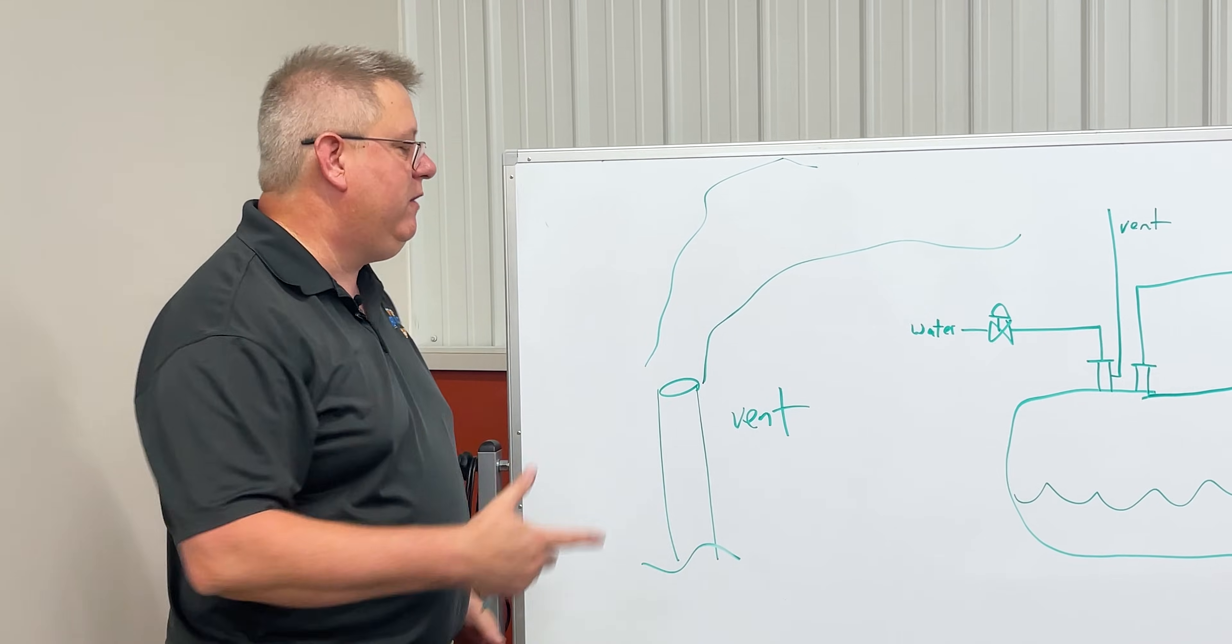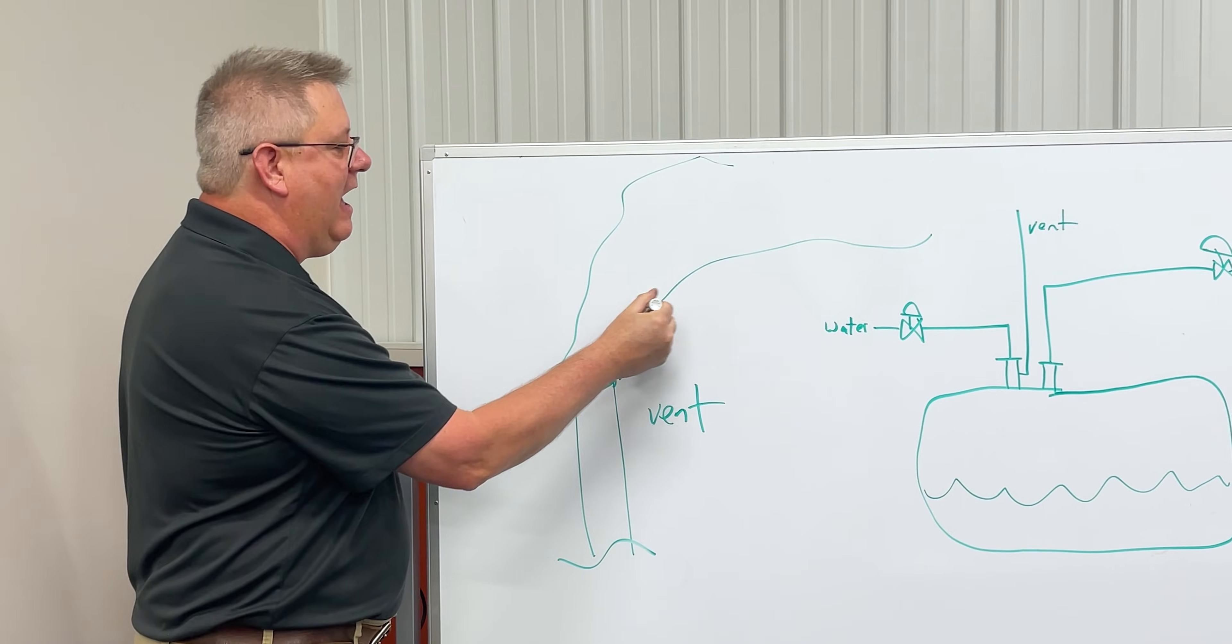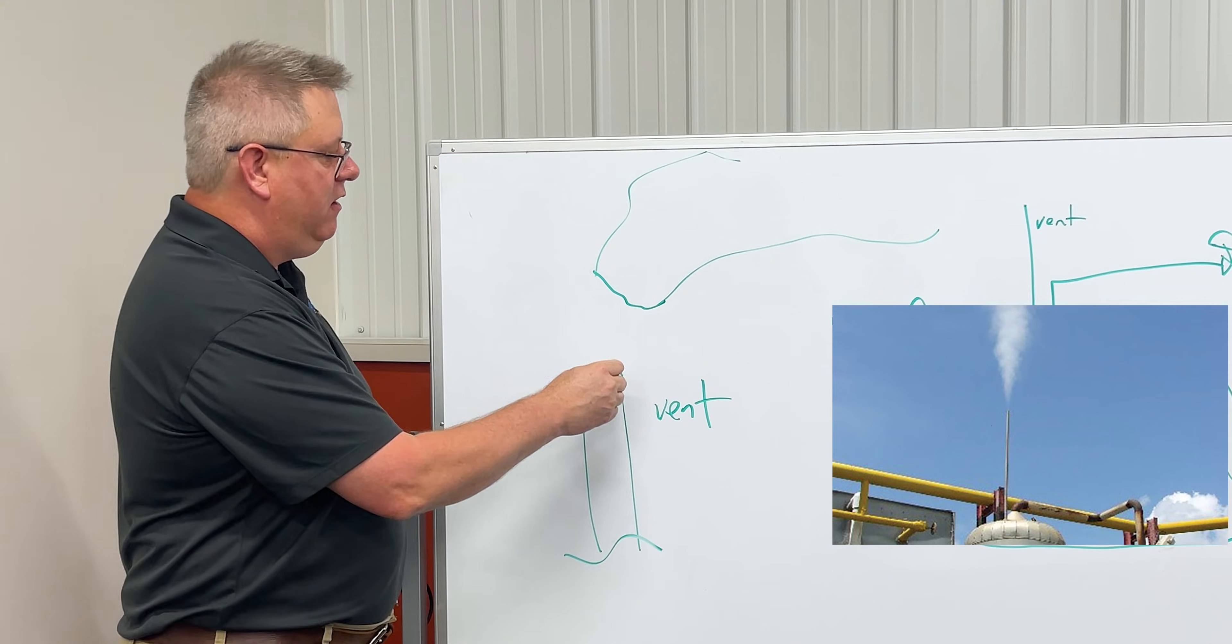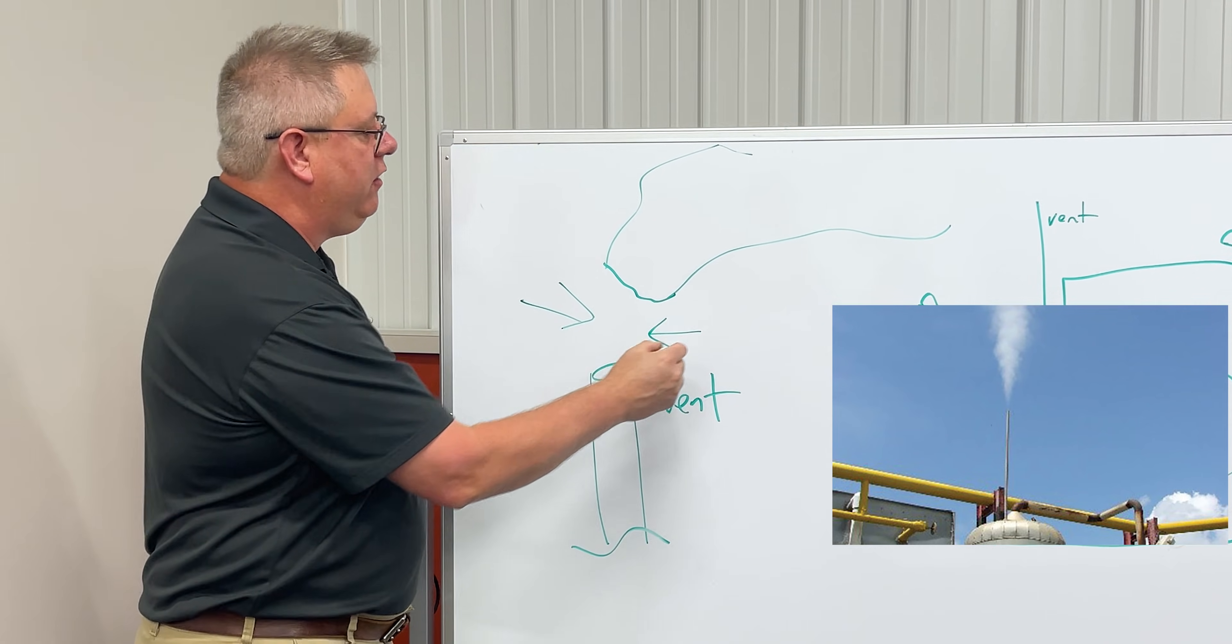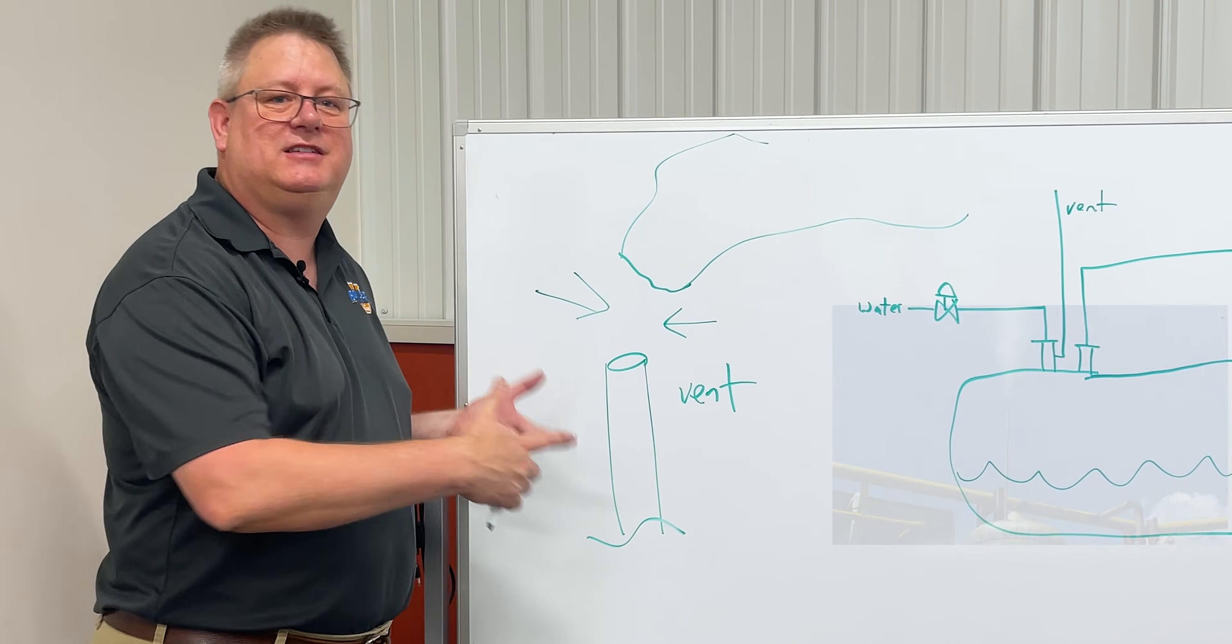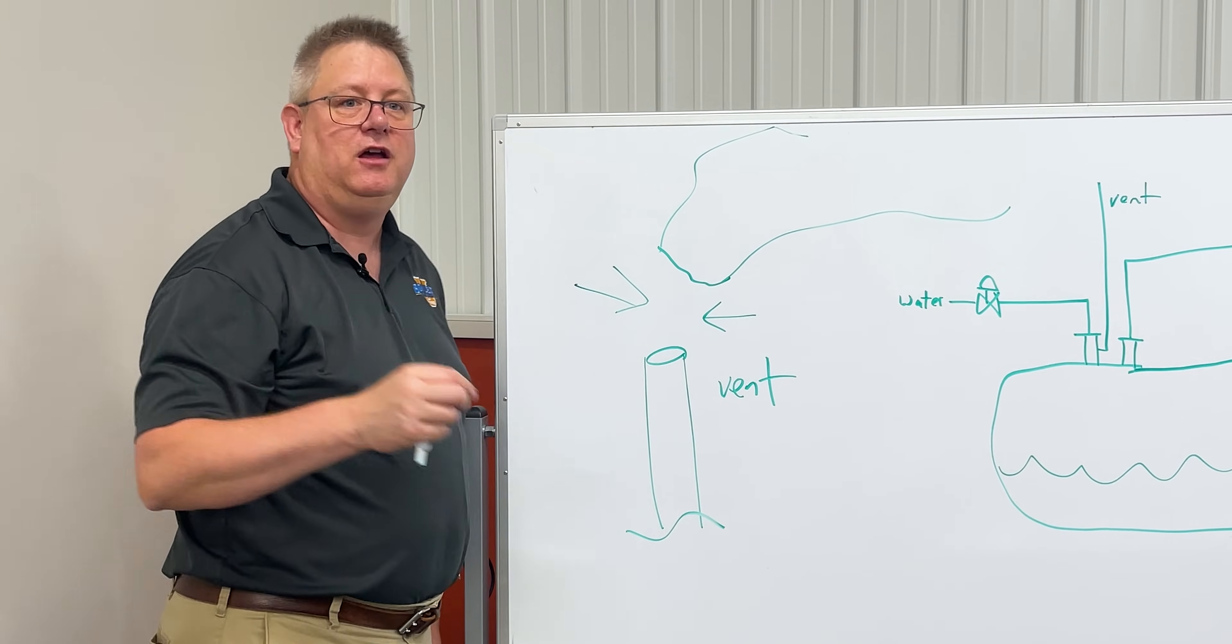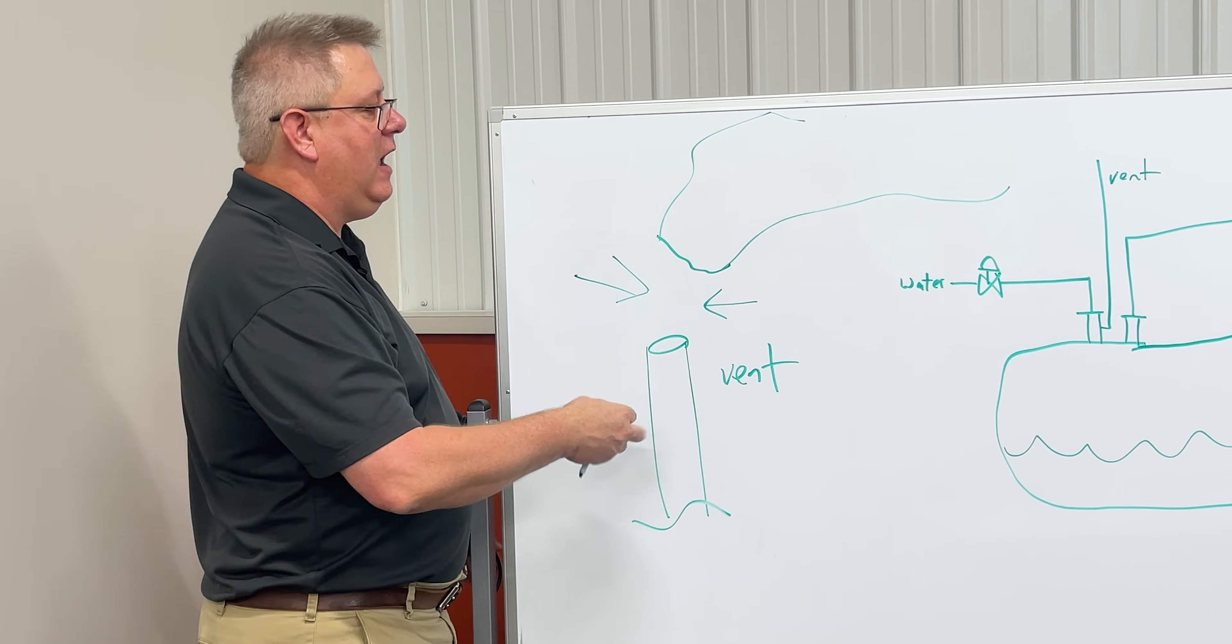If we've left that open from startup, we may actually have a clear gap at the base of the outlet. That invisible layer we see there is pure steam, which indicates we're venting excessively. We can close the vent back to the orifice and look at it again, and it should be reattached.